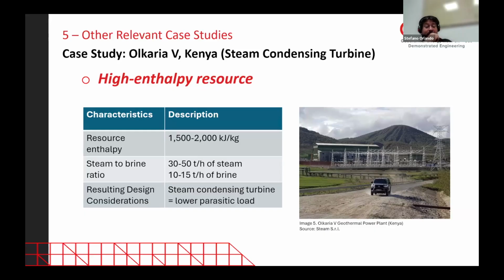And the enthalpy there is very nice because in Kenya they have this potential and very high enthalpy reserves. So the reservoir is typically around 300 to 320 degrees Celsius, and they already have a two-phase fluid in the reservoir. They also have good productivity from each well, and more or less Olkaria 5 had a range of 30 to 50 tons per hour of steam and 10 to 15 tons per hour of brine. So as you can understand, the condensing turbine is somehow forced and obliged by these numbers.